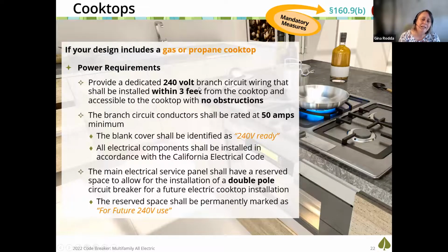Let's say you want to put in a gas or propane cooktop. Great. What you're also going to do is put in the infrastructure for a future electric resistance or induction stovetop, which will be a dedicated 240 volt branch circuit within 3 feet with no obstructions. Now you're going to put in a 50 amp branch circuit.